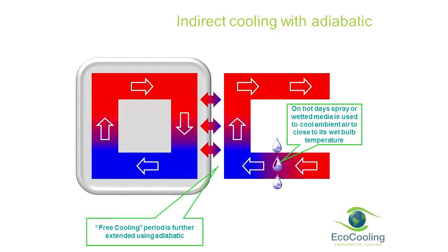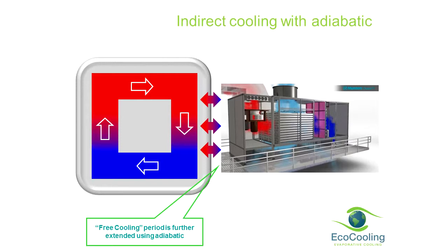So what you've got on any form of air ventilation system, either direct or indirect, is the opportunity to take that air and put it across an adiabatic cooling process and create air in the very low 20s. So that then allows you to introduce a temperature reduction in either direct or indirect, which knocks the temperature out of the ambient air, so you can continue using this free cooling, what people would say, for longer and longer periods. And that's a typical big indirect cooler where you'll see Munters Oasis, X-Cools, and you'll have seen all these types of products around.